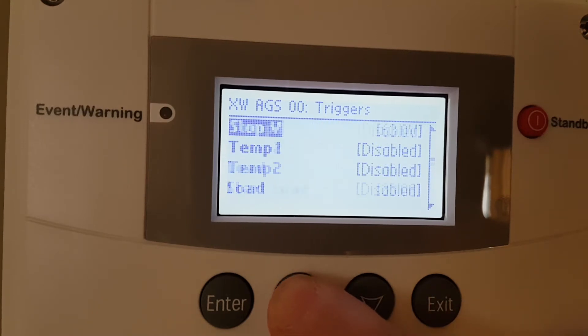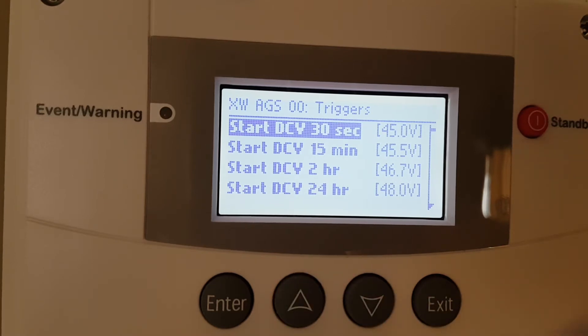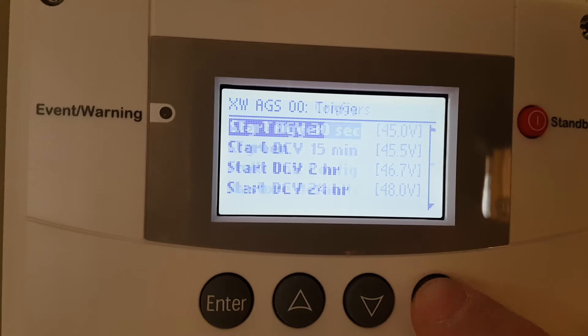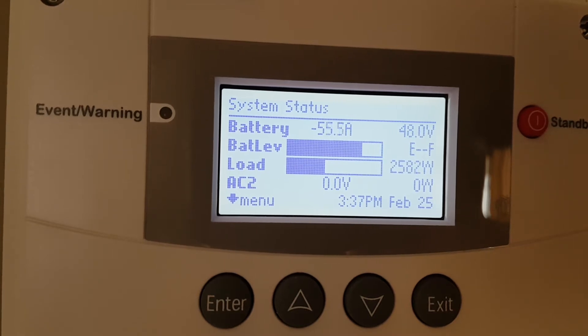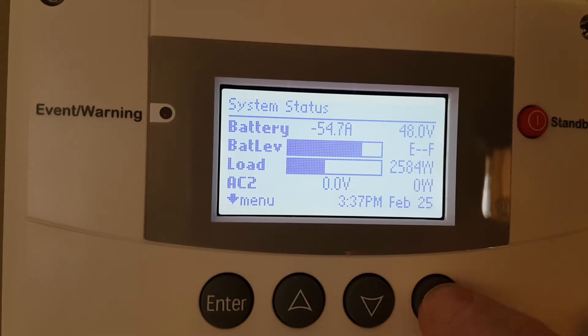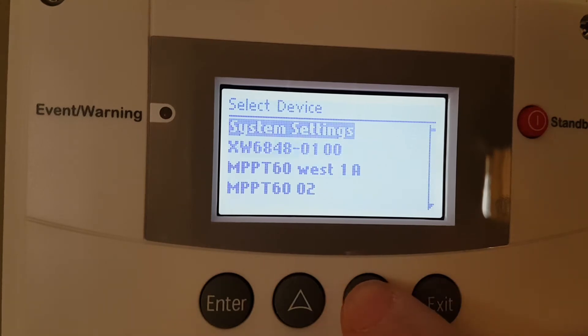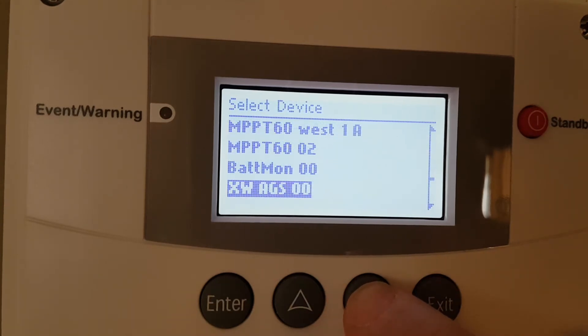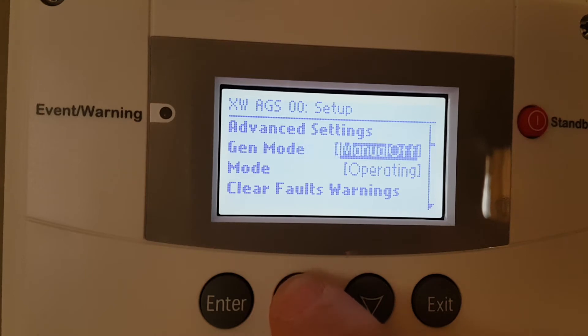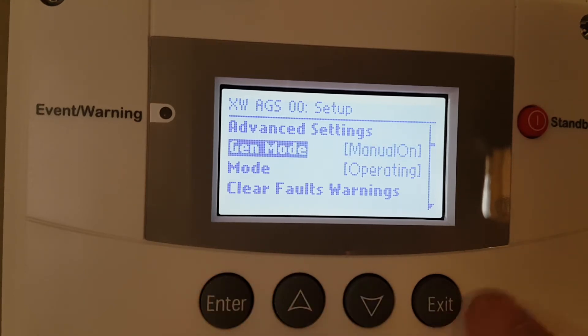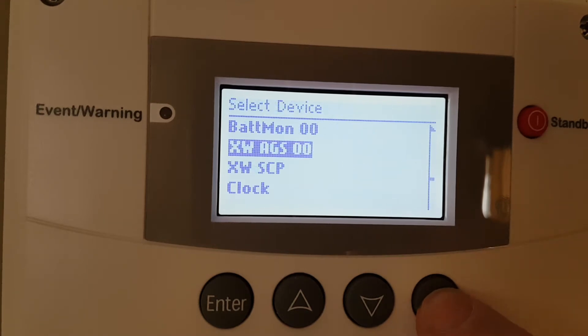So that's about it for that. Going back up to the top — as you could originally see, my generator is going to start at 45 volts. Let's go all the way back, exit, and go back to start to see how much load we've put on it. I'm at 45.8 volts right now, so the generator's not going to start. My load's cutting in and out. What we could do is manually start it. We go enter, automatic generator start, go into gen mode, go into manual on. There you go — the generator's going to start. Exit out of here.